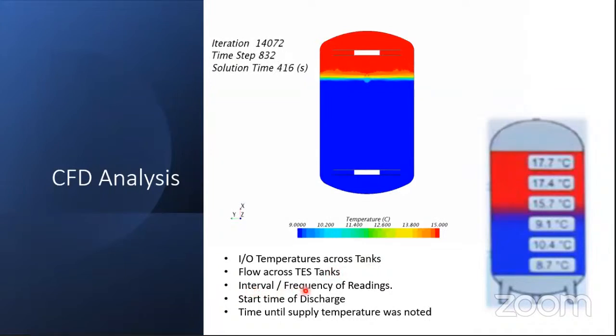Now, the interval frequency is also recorded for all the readings, that is, when it was recorded. That is also summed up to calculate the duration, let us say 5 minutes, 10 minutes, whatever it was, or even hours for that matter, in a larger system. So that is summed up and converted in terms of hours. And when we multiply these tons and these hours, we get the ton-hours. So the TRH for which we planned the system, that is something that we can practically calculate also. This is an assessment which is done during commissioning. This is the performance testing which is done at the time of commissioning.